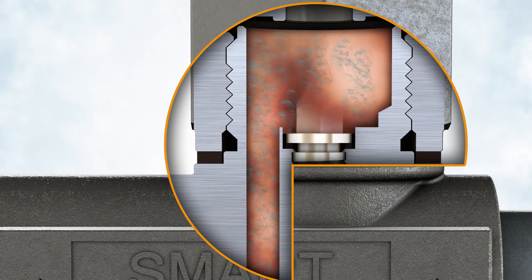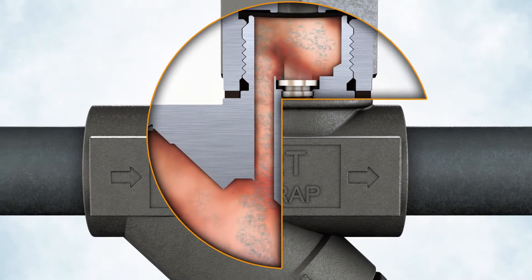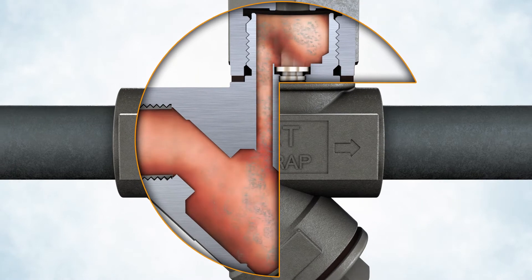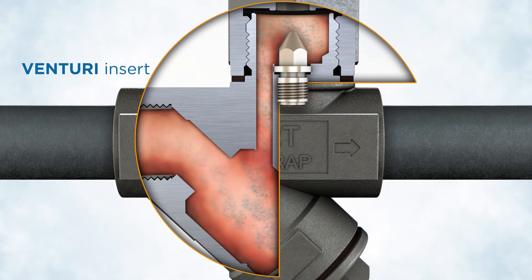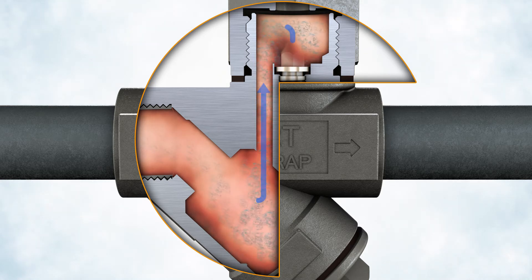The diameter needed for each application is selected based upon pressure differential and condensate load. Second, a portion of the capacity is controlled by the back pressure that is generated inside the venturi insert using flash steam.